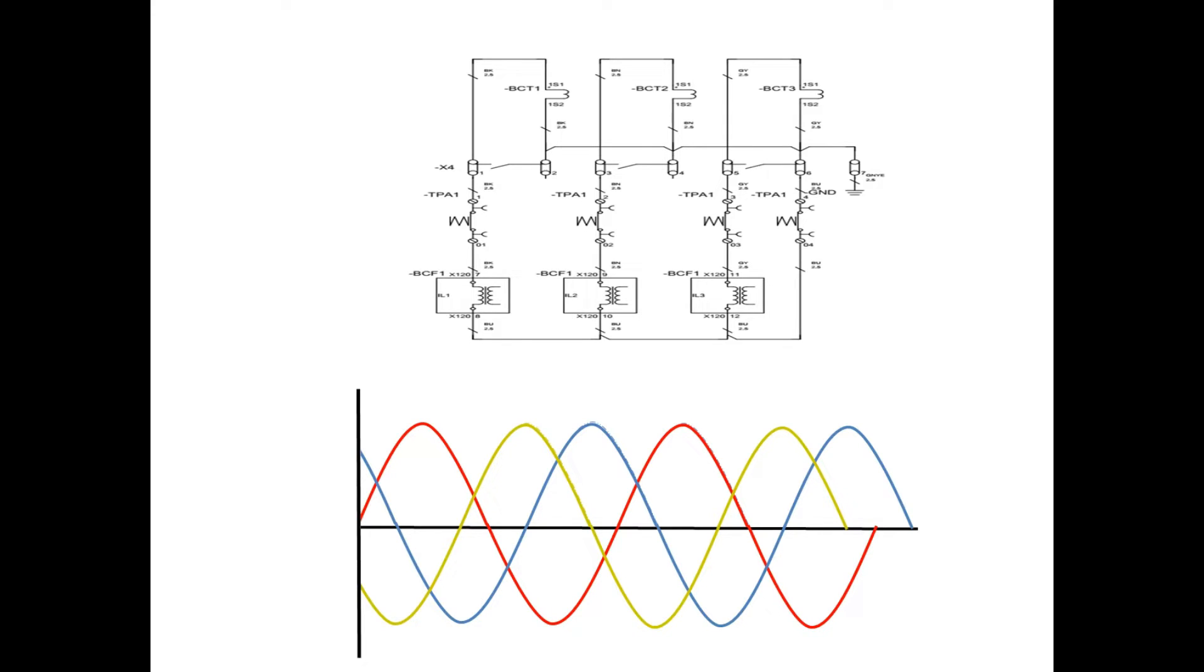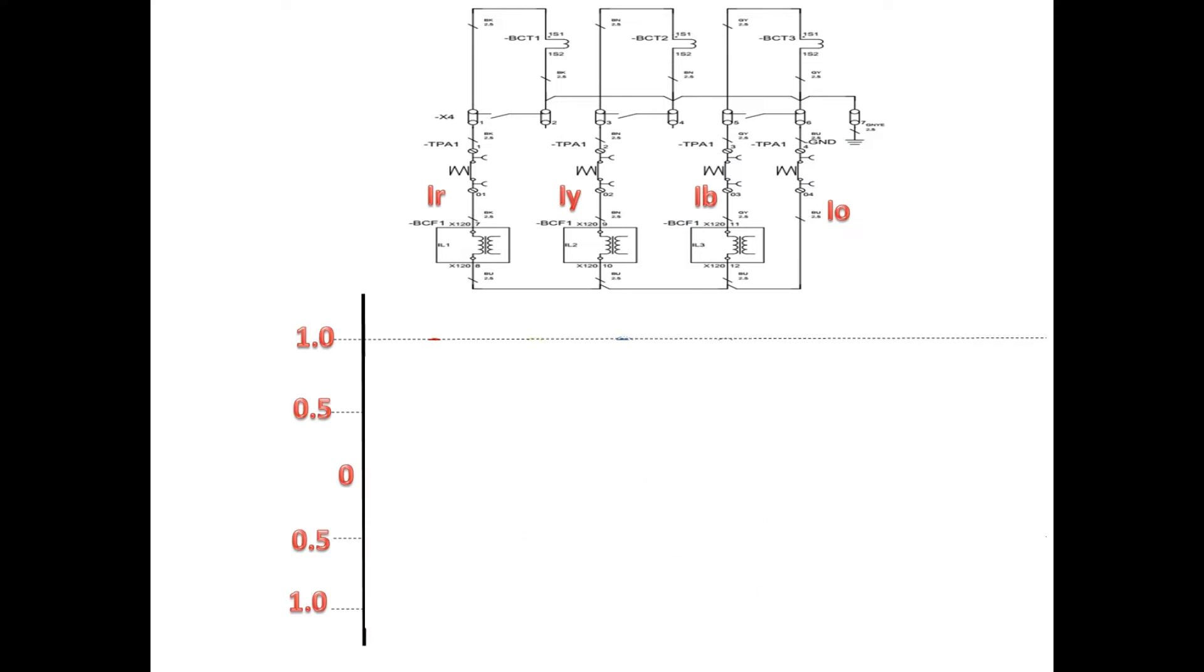On seeing this circuit, we can clearly identify that R phase has three possible ways to have its return path. One way is it can flow through Y phase CT and return to this path, or B phase CT and return to this path, or neutral path. Because the CT connection always has low resistance, the current can flow to all these three paths.